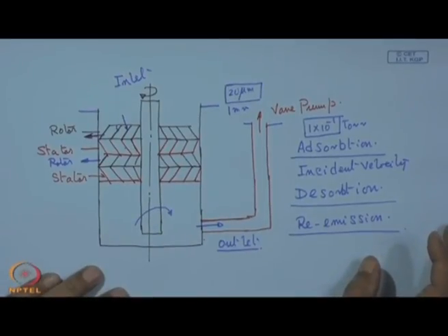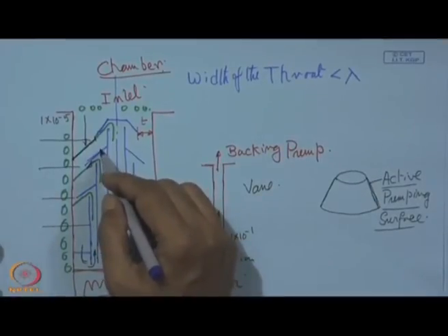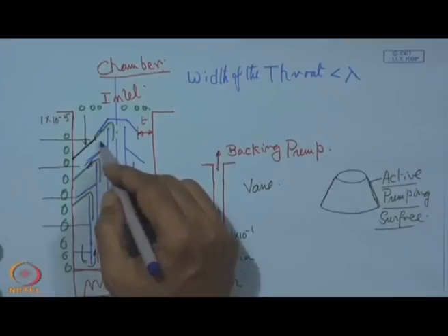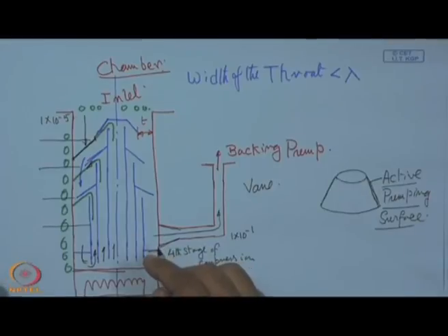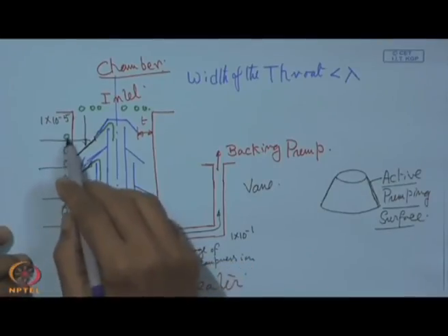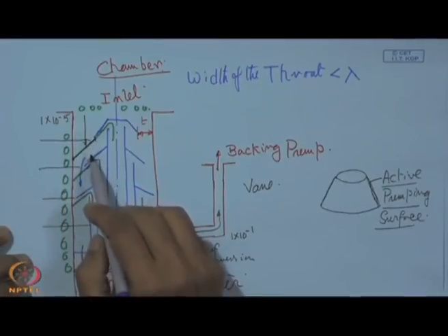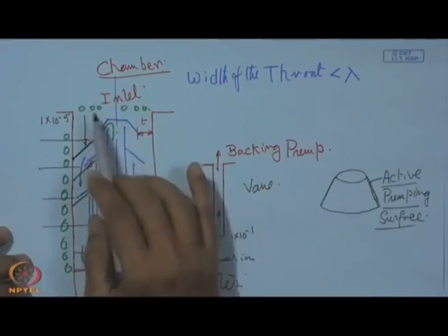One of the greatest advantages of this pump with respect to the diffusion pump, we can have a quick look here. When we discussed the diffusion pump, we always assumed that there is this deflection, and that is in the downward direction. But for an unfortunate eventuality, if we do not have proper cooling and condensation, if there be some backstreaming of this vapor, that can contaminate the chamber and the specimen. But such a thing we do not foresee in this case.